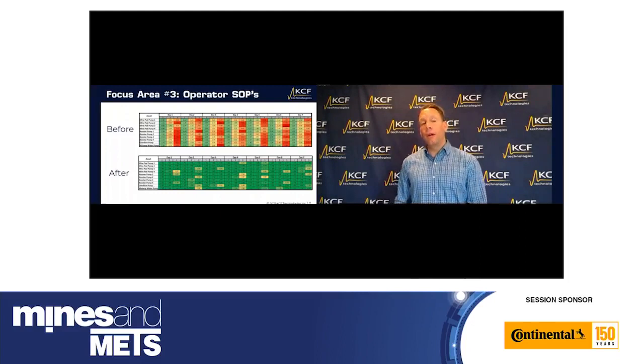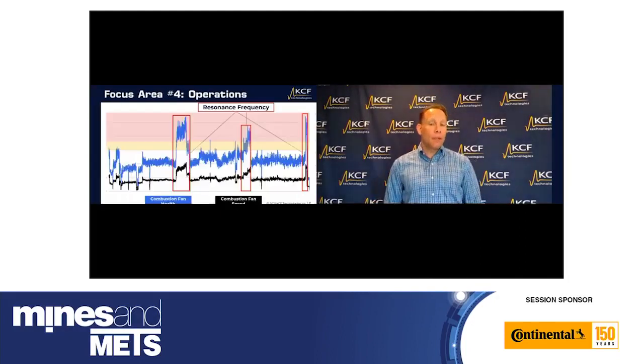Now, the fourth and final topic related to operations is resonance. What we see, and this is especially on fan systems, but we also see it on shakers and conveyors, is that there are certain speeds programmed into your controls that are not healthy for your equipment. And we can help you identify where those resonance frequency areas are, those high damage blind spots, and reprogram your controls to eliminate them entirely.